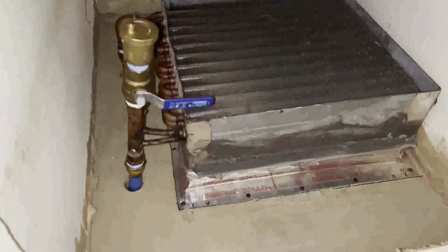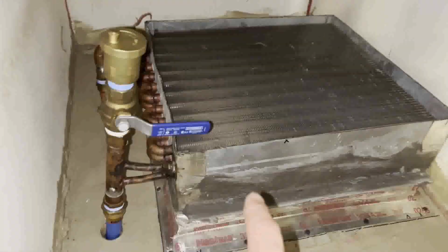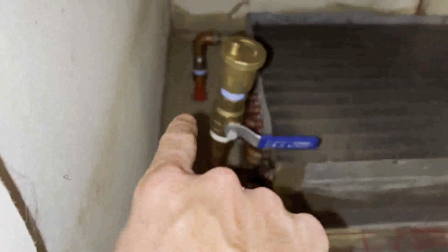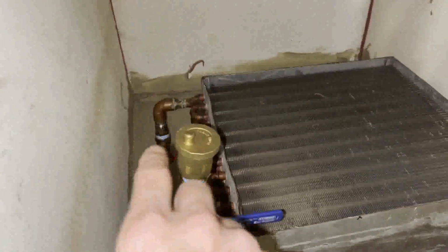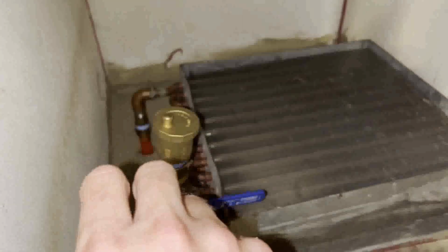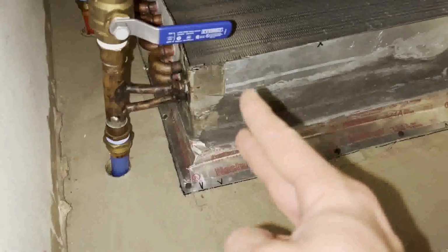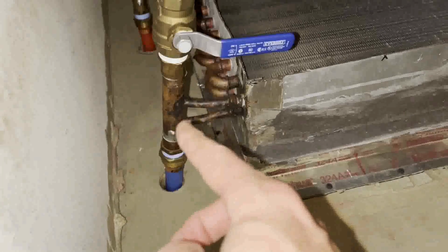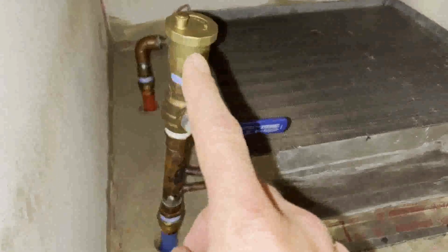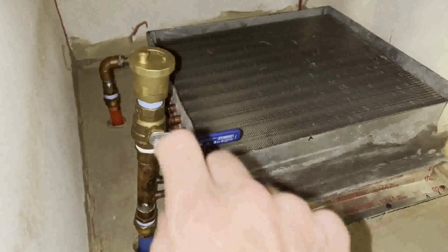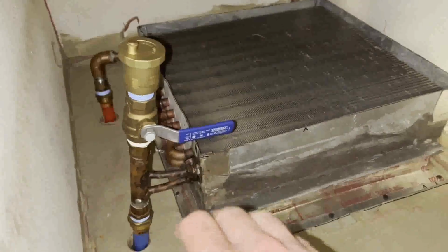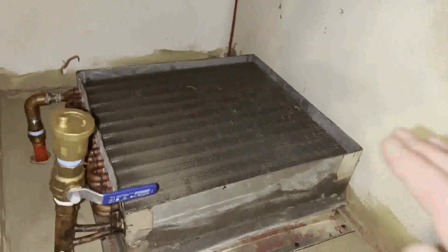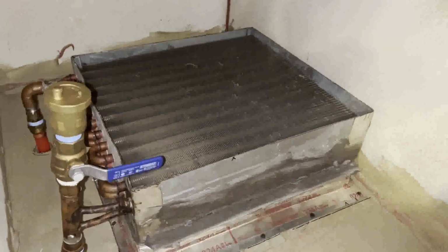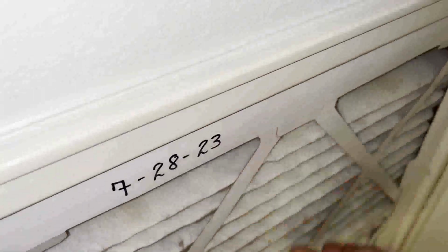All right, so this is a return plenum, and there's a hot water coil here. You can see the red line there. Hot water comes in. This is a 2-circuit coil here. So it's 2 rows, it's dual rows. So that water goes through like that, comes out here. So we braze that in to this 3/4 pipe. There's an air vent. These are automatic air vents, but I have seen them leak over time. The little float in there doesn't seal. So once you bleed the air out, you should be good, unless you start leaking. But the air comes in here, return air, goes down and gets heated and comes out the vents all hot. So we will close this back up.